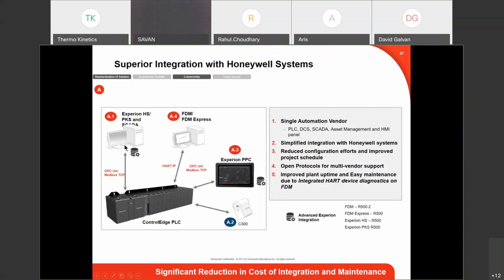The PLC also has universal I/O. So every card you see here is 16 channels of universal I/O. I can software program every channel to be either an AI, an AO, a DI, or a DO. And the cool thing too is that every one of the 16 channels has its own dedicated HART MUX modem on it. So now I can access, interrogate, and configure the instrument that's connected to that channel utilizing FDM, through OPC UA HART IP.